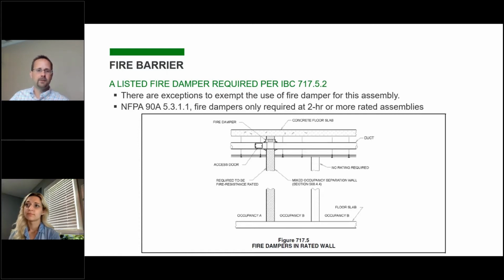The IBC has several exceptions, and the exceptions range from having a UL listed assembly, which is the same with all these different wall types we're going to talk about, or if it's a part of an approved smoke control system. That's an exception that's pretty common throughout all these walls, so we're not going to go into that in detail as well. The biggest one for fire barriers is exception 3 in the code, where it discusses that a wall penetrated by a fully ducted HVAC system, and the wall is 1 hour or less, you have a fully sprinkled system, and it's constructed of 26 gauge steel that's continuous from the air handler to the air inlet or outlet, that fire dampers can be omitted in those 1 hour or less fire barriers.